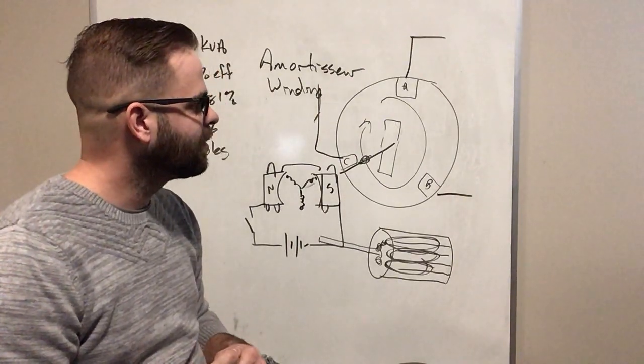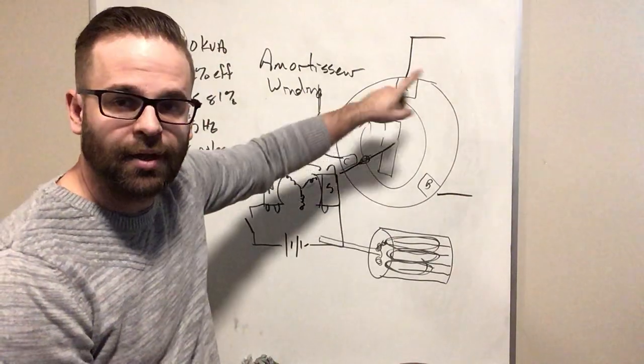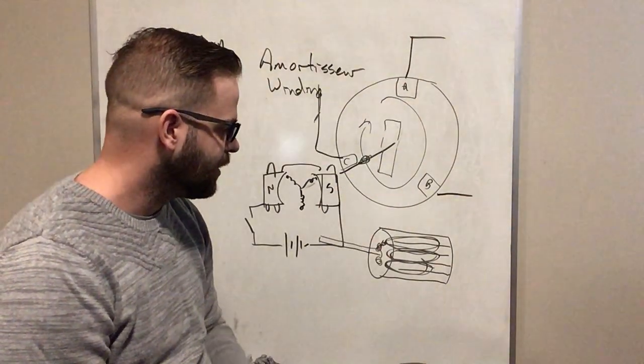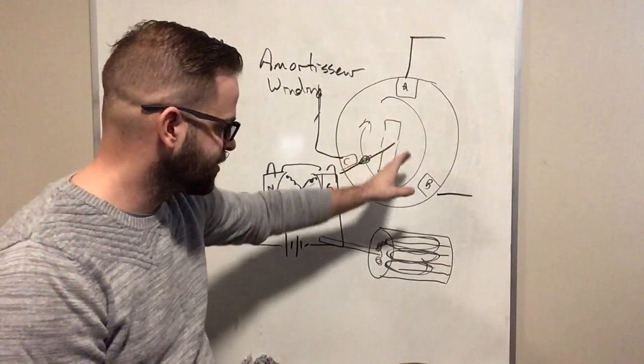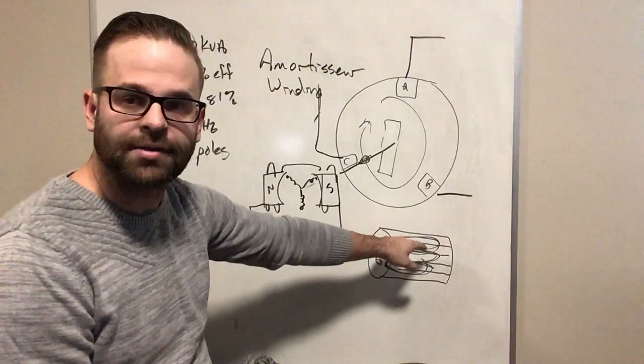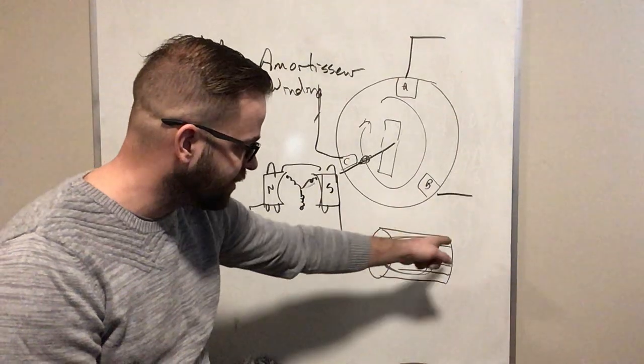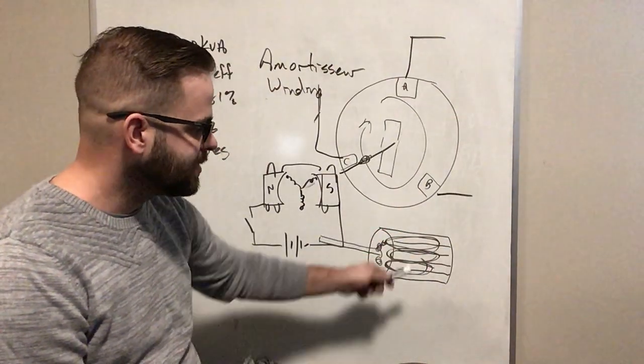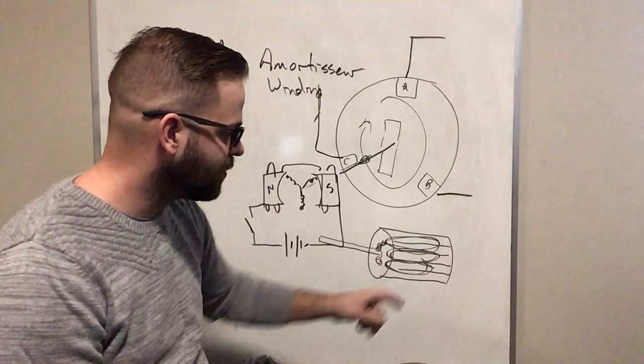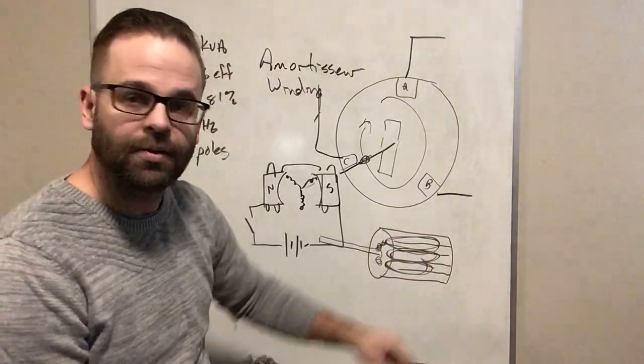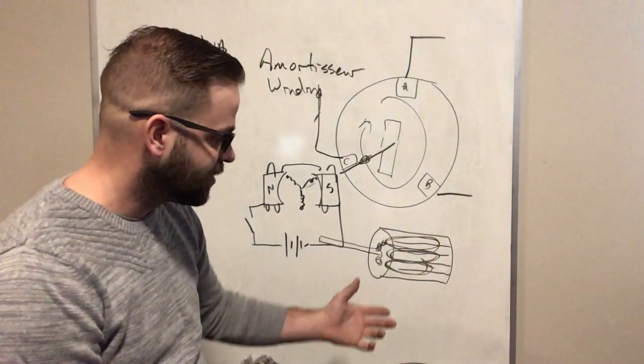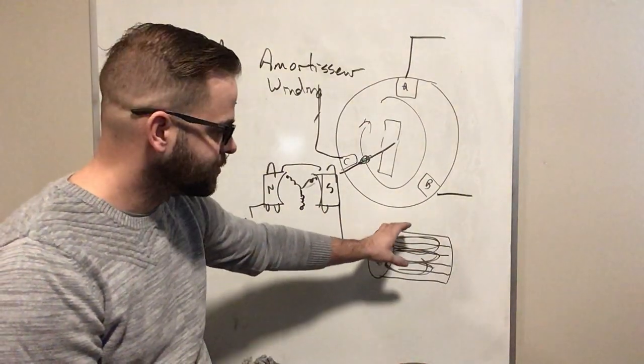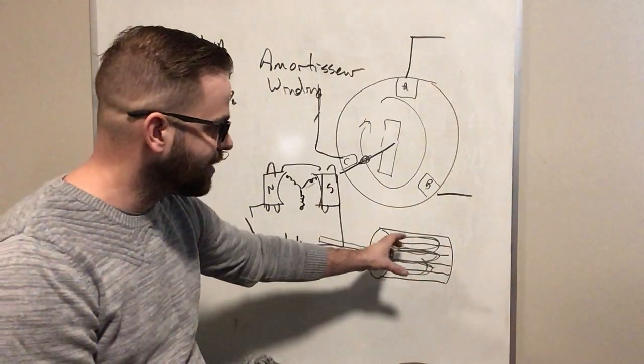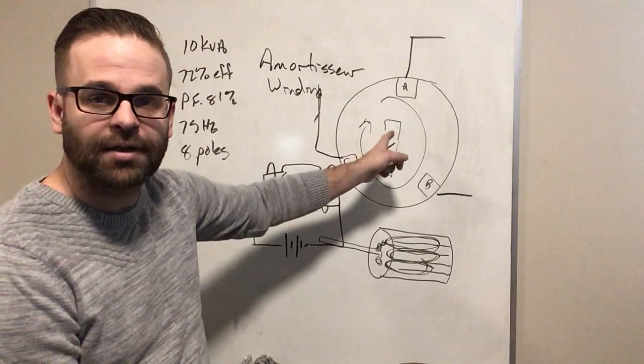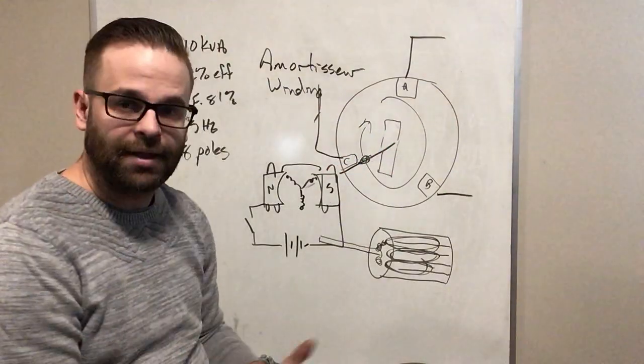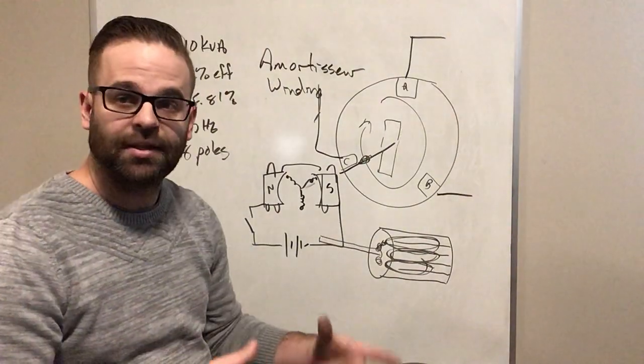So if I end up having a magnetic field traveling around inside this motor, those magnetic lines of flux are going to end up wrapping around and cutting past the bars of this amortisseur winding. And if I have a completed circuit, so I have a path for current to flow, as those lines of flux cut those bars, I'm going to end up inducing a voltage and current into those bars, which in turn is going to produce a magnet. So I'm going to produce magnets or a magnetic field on that amortisseur winding, and that magnetic field is going to be attracted to the magnetic field of the rotating magnetic field, which is obviously going to spin the shaft of that motor.